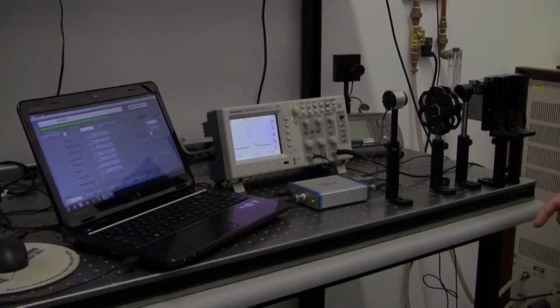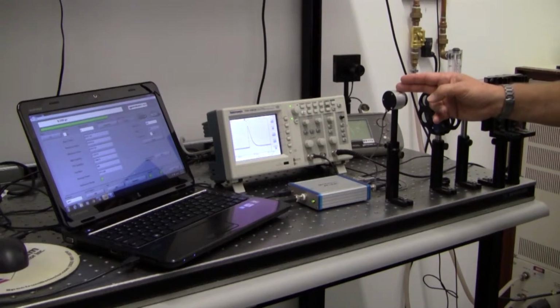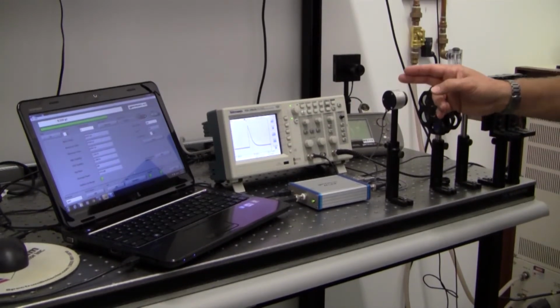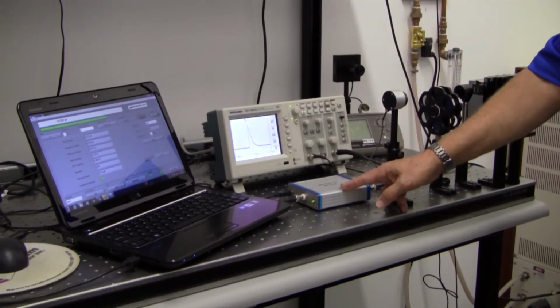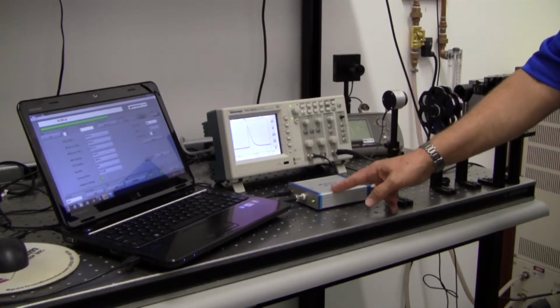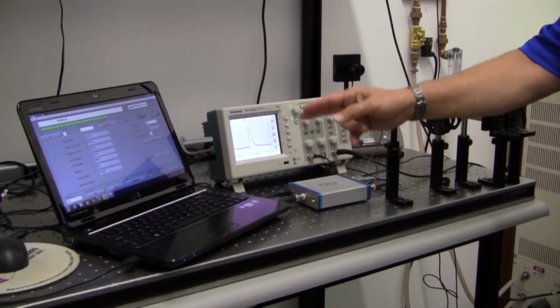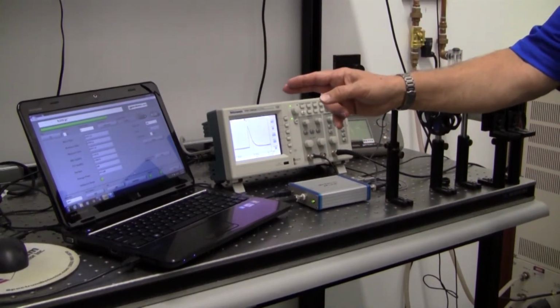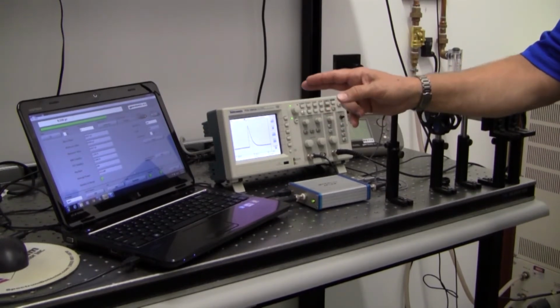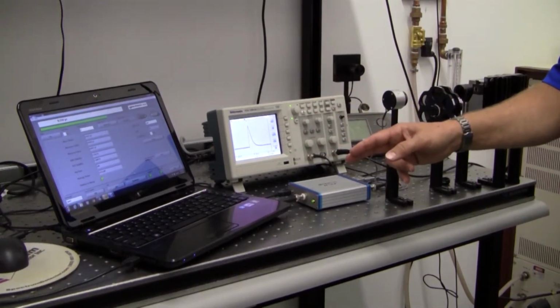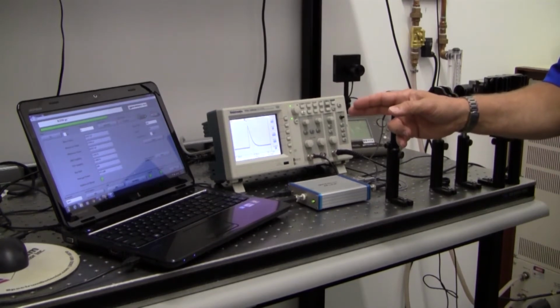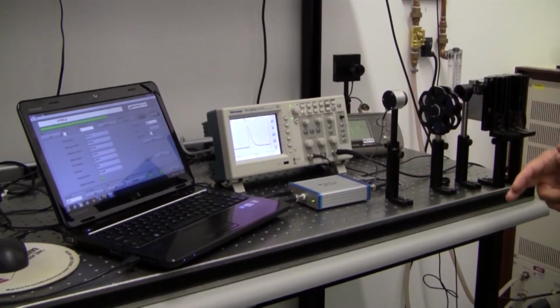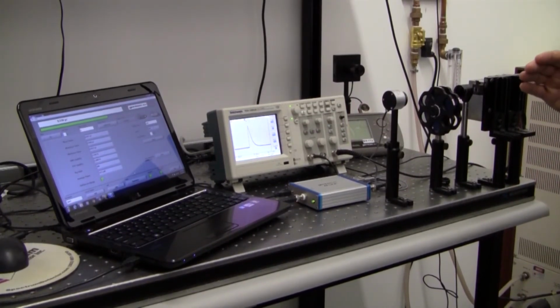To summarize, you need to use one of our PE3B SI probes mated to our digital joule meter M-Link using the external trigger. You need to set the software up for an external trigger and engage our noise suppression software set to 128 pulses. And you need to make sure that you've eliminated all the background light in your test measurement setup.